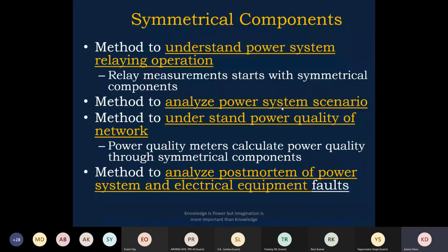And it is a method to understand the power system quality of the network. When harmonics are involved, power system quality depends on the total harmonic distortion of the waveform. When harmonics are introduced into the fundamental component, they distort the sine wave, and negative sequence or zero sequence components get introduced. We will see in the next slides how to analyze this. Power quality meters calculate power quality through symmetrical components, a combination of harmonics and symmetrical components.